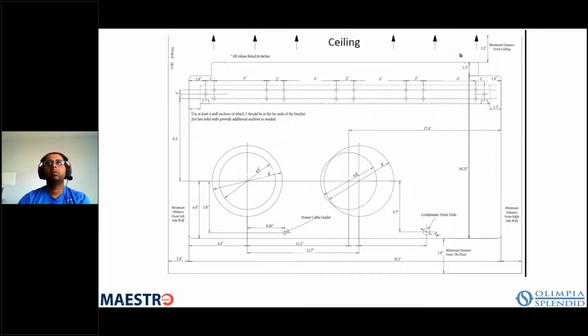And there's a look at the template itself. I wanted to point out here that the holes that you have to drill or cut for this unit are either 8-inch round, you see here just 8-inch, or 6.4-inch, okay? And you can see both holes are laid out here for both the air intake, which is what you see here on the right, and the exhaust is what you see here on the left. So you can install this unit with two 8-inch holes, an 8-inch duct, or if the geometric constraints on your job won't allow for two 8s, you'd have to go with two 6.4s.